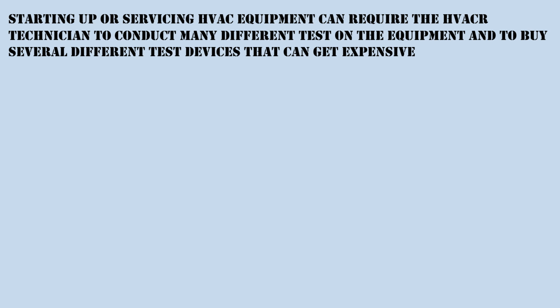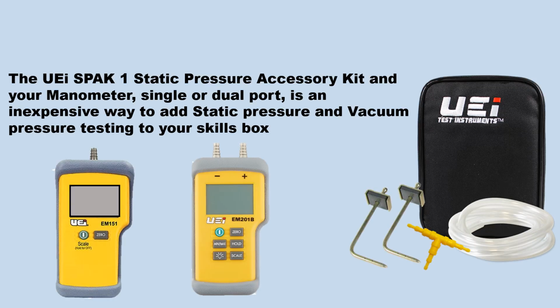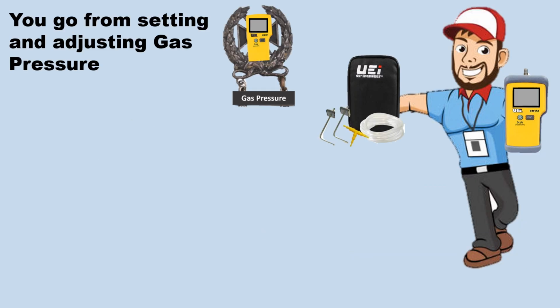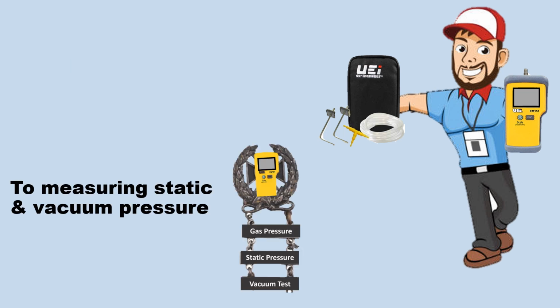Starting up or servicing HVAC equipment can require the HVACR technician to conduct many different tests on the equipment and have the need to buy several different test devices that can get expensive. The UEi SPAK1 Static Pressure Accessory Kit and your manometer, single or dual port, is an inexpensive way to add static pressure and vacuum pressure testing to your skills box. You go from setting and adjusting gas pressure to measuring static and vacuum pressure with it.